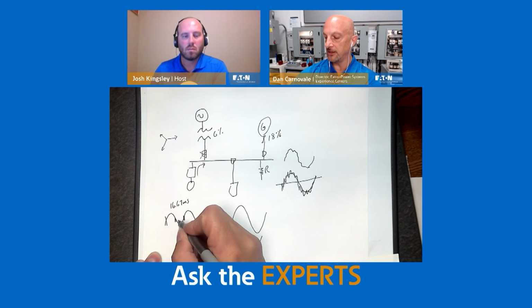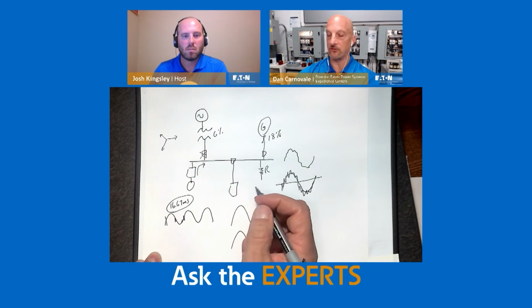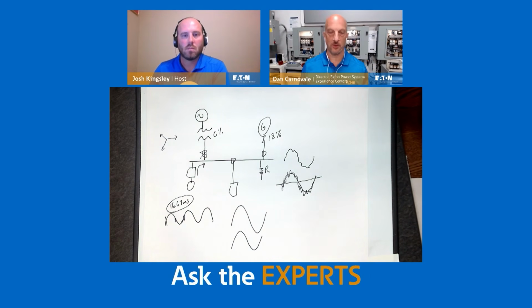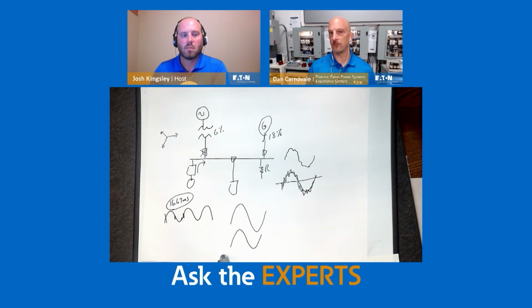Well, if it crossed there and here and maybe over here again, now every time it crosses zero, it thinks that's 16.67 milliseconds. So the welding line that was supposed to be 20 times that was only getting 8 times that. They were having bad welds and stuff. So again, harmonic problems are a little bit difficult to track down after you have this issue, because it's not always just like something overheats and burns up. It's something that over time heats and burns up, or this misoperation is a little bit intermittent. Like sometimes it does it, sometimes it doesn't. So again, the things with the generators, and especially with voltage distortion that gets pretty bad, can be difficult to track down, but it also follows that simple rule of electricity, which is Ohm's law.